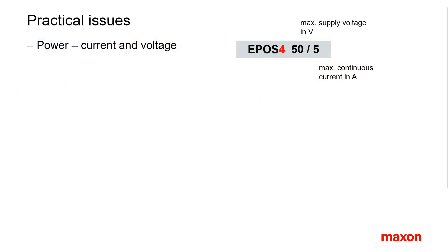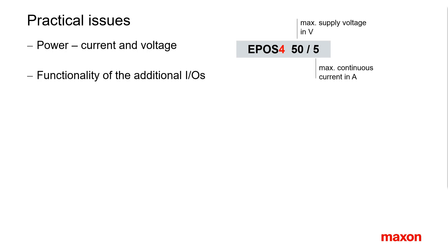Some practical issues when selecting a controller: power. The main difference between the different versions within one controller family is the supply voltage range and the current capabilities, as indicated in the designation. The maximum current rating is typically two to three times higher than the continuous current rating and can be sustained for up to a minute. Between different controller types, there may also be differences in the number and functionality of the additional IOs. Select the version that best fits your application.